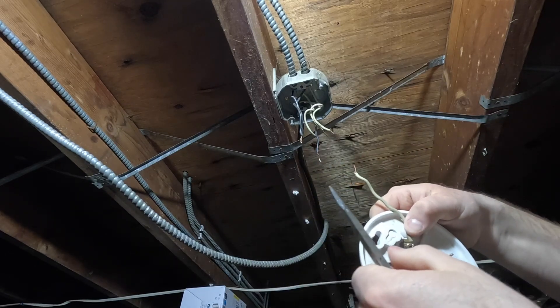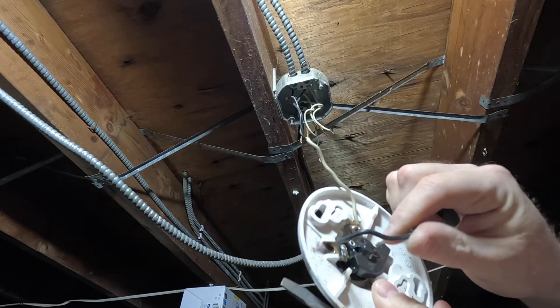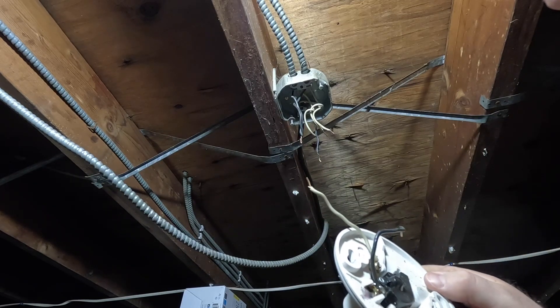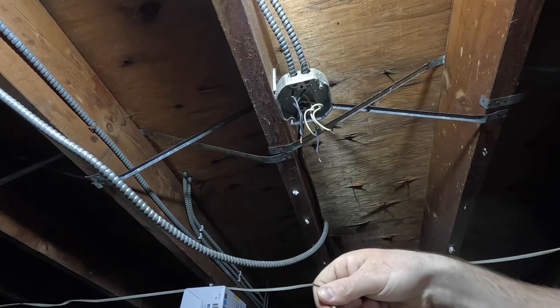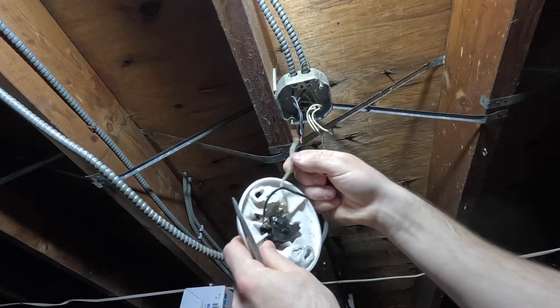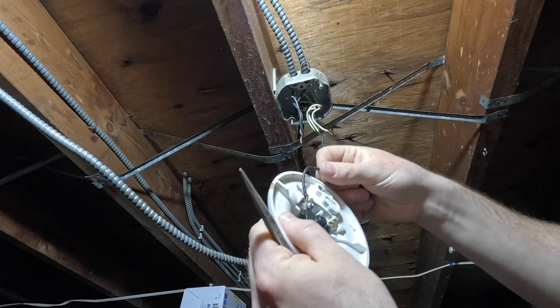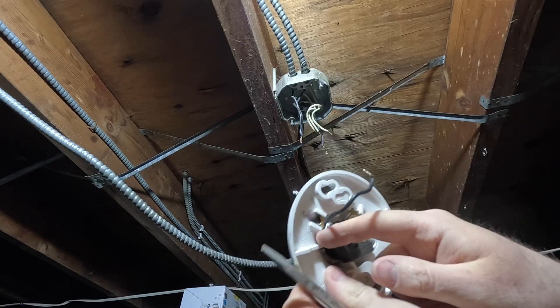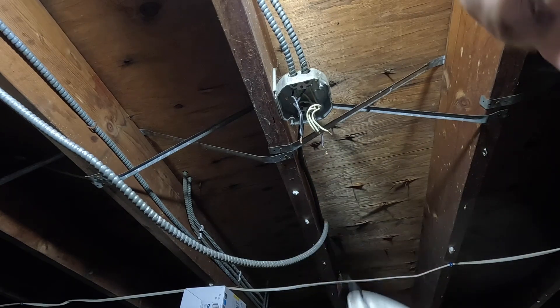Wow, look at this arcing on here — it's actually almost welded itself on. Good grief, that is not good. I'm going to replace these leads, which are about to come off anyway, with new wire. This way if this does go bad in the next couple months before I get it replaced, it won't contaminate the fixture. Look at this — that just came right off. I think it might be arcing right there, which is kind of weird — maybe we'll check that on a different video.